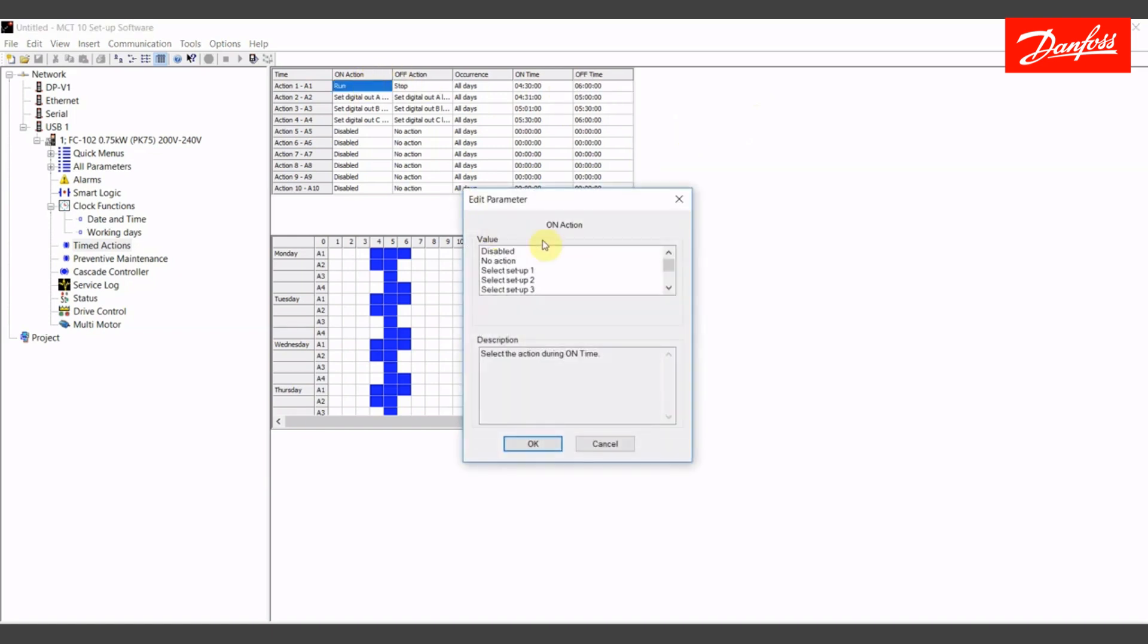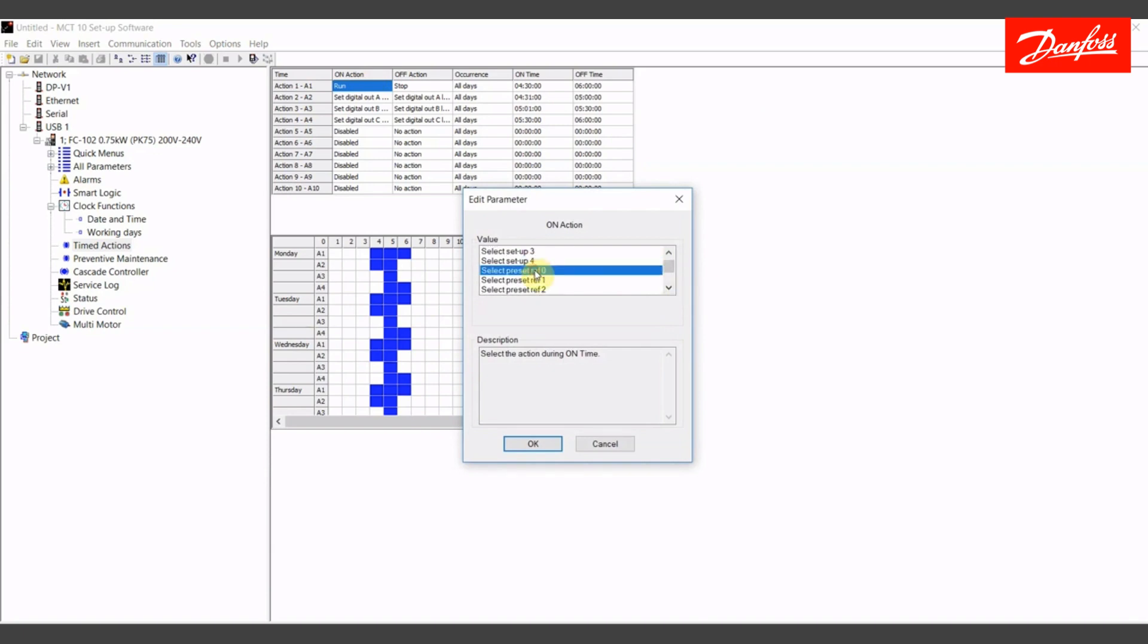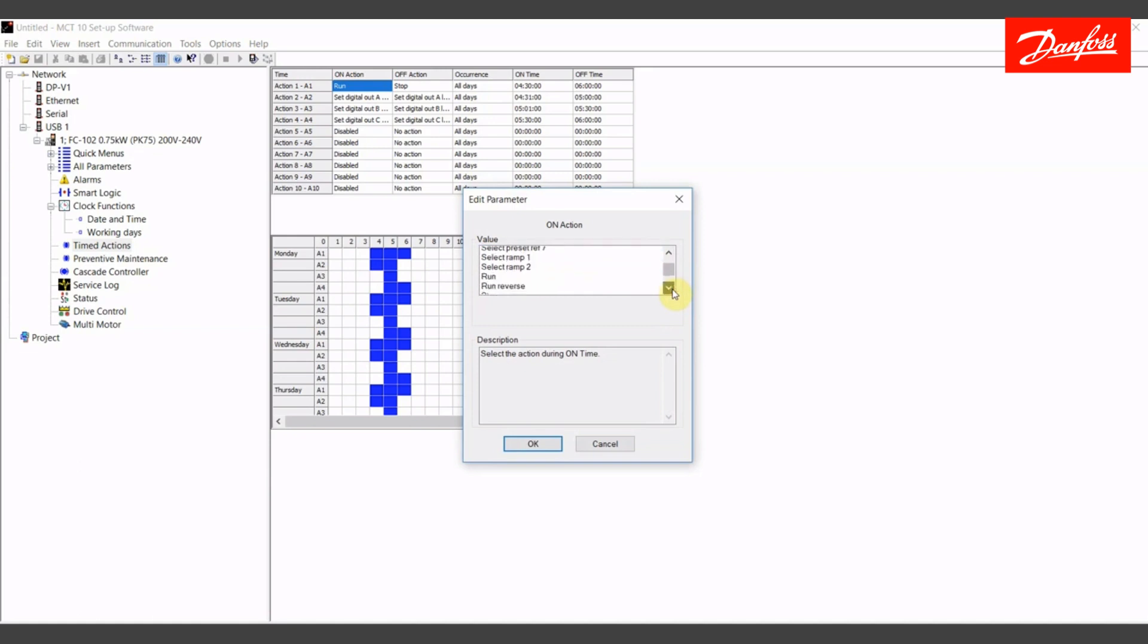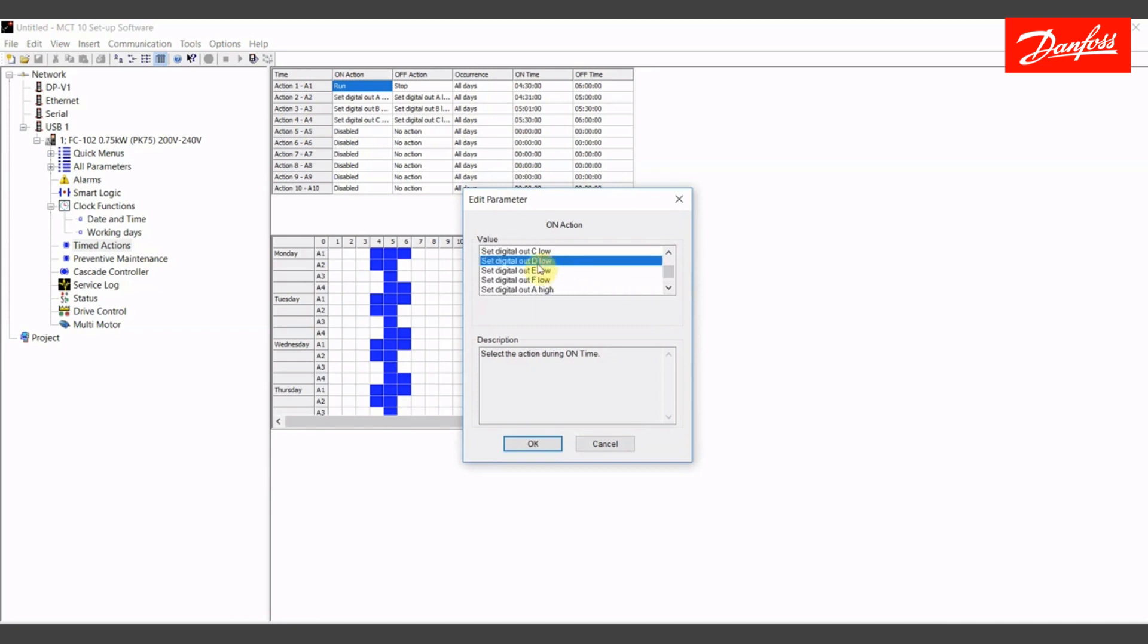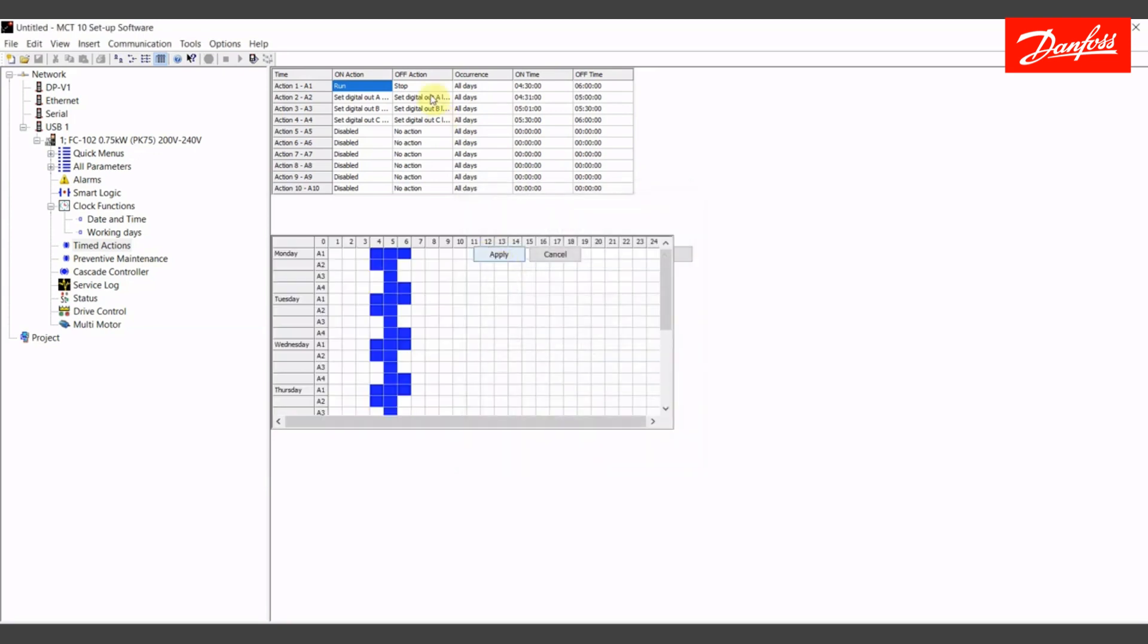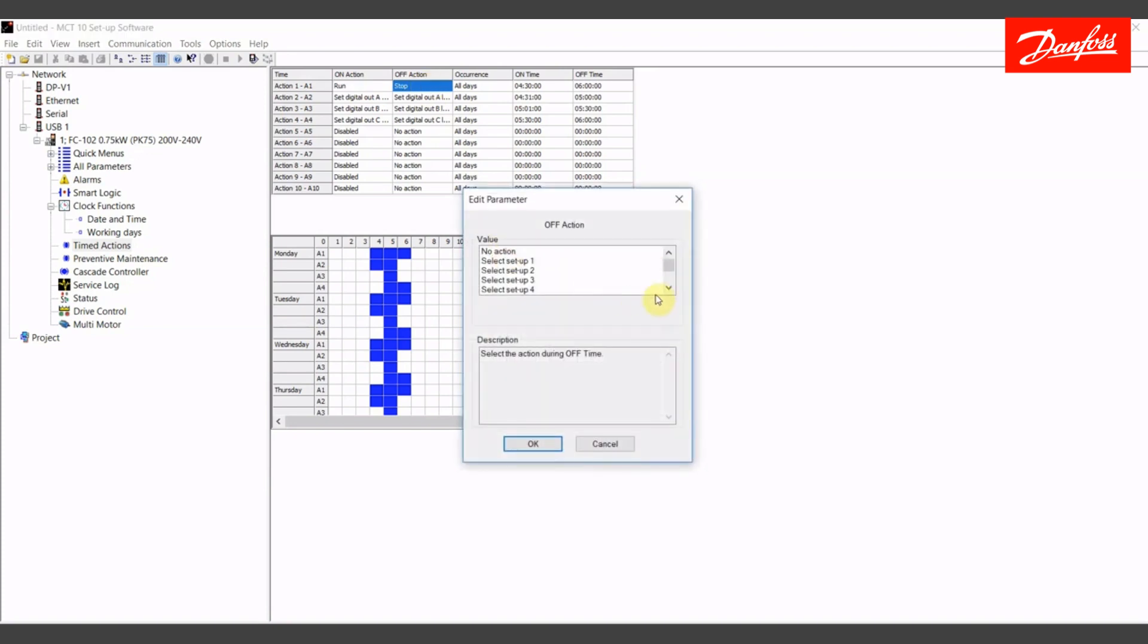Our first on action, I have selected the value run. I want to point out here that there's a lot of things that you can do with this other than just starting and stopping the drive. I can change preset speeds, change setups, ramps, direction, setting an output high and low. That is turning a physical output on and off. So we're going to do that in the next event. My on action will be to run. My off action will be to stop.